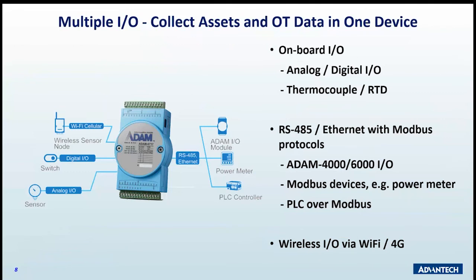So, multiple I/O on the device itself, like the ADAM series previously - standard analog and digital I/Os, with the ability to connect things like temperature sensors, thermocouples, and RTDs. It has RS485 built in, Ethernet with Modbus protocols, it's all there. It can seamlessly connect with the ADAM 4000 series, which is serial-based only, and the 6000 series, all over networking, and it also has the ability to go wireless, Wi-Fi, or even 4G.